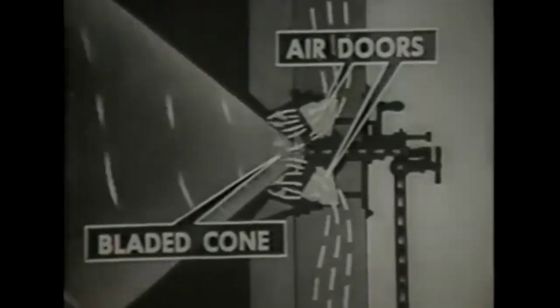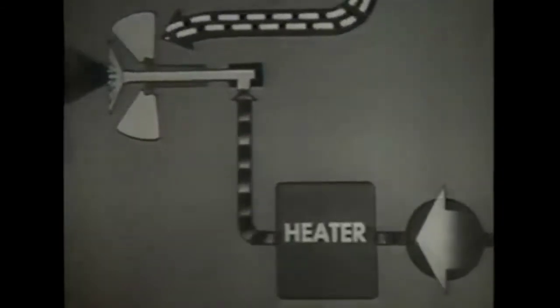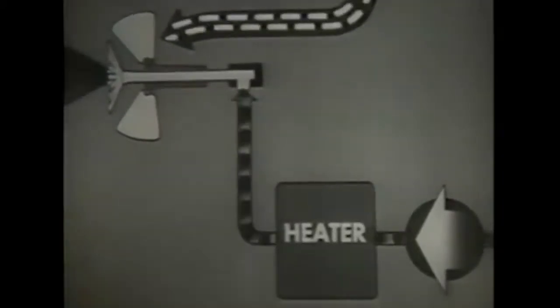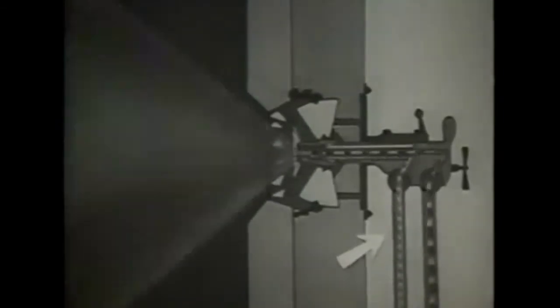In burners with mechanical atomizers of the pressure type, the sprayer plate atomizes the oil, heated and under pressure. The register gives the blast of air from the blower a rotating motion and mixes the air with the oil. You vary the pressure on the oil supply line to control the amount of oil entering the furnace. To control the amount of air entering the furnace, you vary the speed and number of the forced draft blowers. In the return flow burner, you vary the pressure on the return oil line to control the amount of oil entering the furnace.